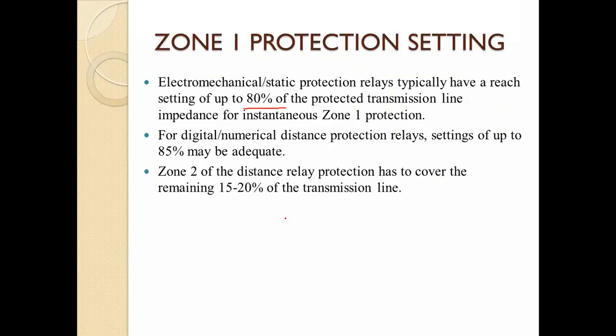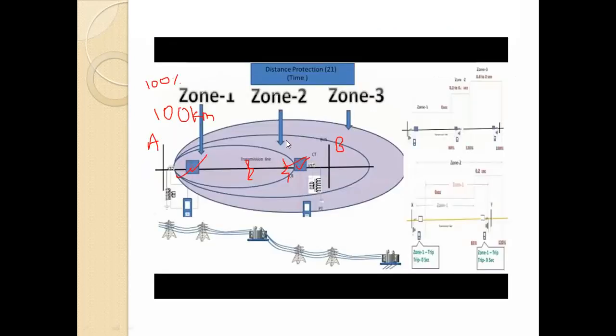Meaning, out of your 100 kilometer line, 80 kilometers of it will be completely protected. Meaning, if any fault occurs, instantaneously your relays will start operating. And zone 2 of the distance relay protection has to cover the remaining 15 to 20% of the transmission line. Now in the first zone, how much do you cover? 80%, the setting is 80%. The remaining 20% line, in what will that be covered?